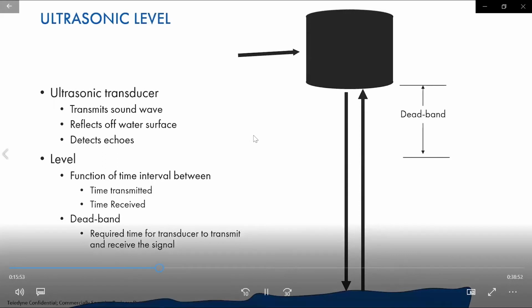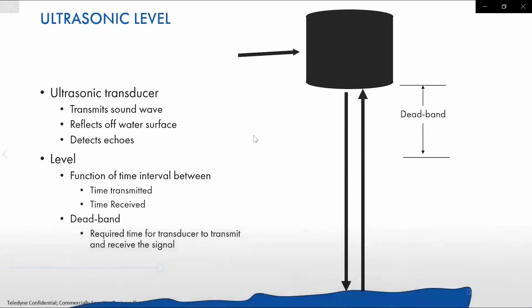One thing that's important to remember about that is if you have your sensor too close, it's in the deadband and the sensor doesn't have enough time to respond and receive that return signal. And you may find that when you have high levels and you mounted the sensor too low, all of a sudden your sensor goes into error.